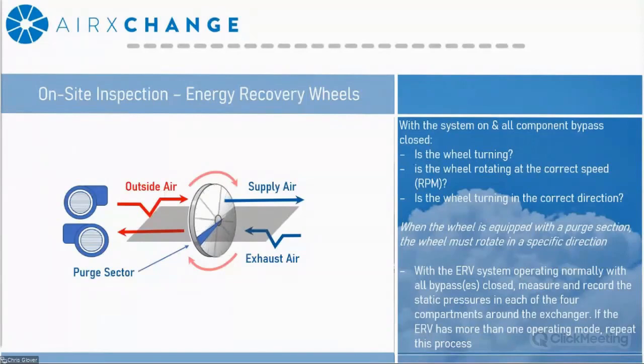Now you're going to want to make sure that the wheel's spinning in the correct direction. I will say that this is usually more critical for units equipped with a purge, because if it's operating in the wrong direction, it can actually siphon air rather than minimize recirculated air. So, once again, some VFDs have a role in this parameter. And with the system in its normal operating mode and with all the bypass dampers closed, you're going to want to measure the static pressures in each of the four compartments that surround the heat exchanger. If the unit has more than one operating mode, you're going to want to repeat this for any subsequent modes.